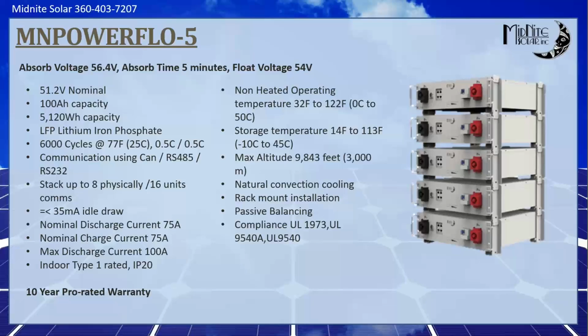Maximum altitude of 9,843 feet. You could probably push that a little bit more. That is just the minimum listing that we listed to. The BMS is conformal coated. Everything is fairly safe in there. They are naturally cooled, no fans, and as I mentioned before, 3U rack mounting. So any standard 3U rack. And compliance, UL 1973, 9540A, and 9540.